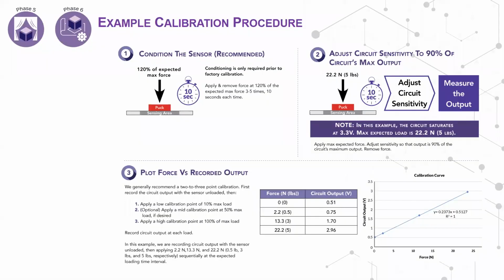So here is an example of a 3-step calibration procedure used for this type of an application. When calibrating FlexiForce sensors, you want to use a completed assembly or as close to a completed assembly as you can. Use force levels within the expected application force range, and also use as close to the same load duration as expected during the application as possible.